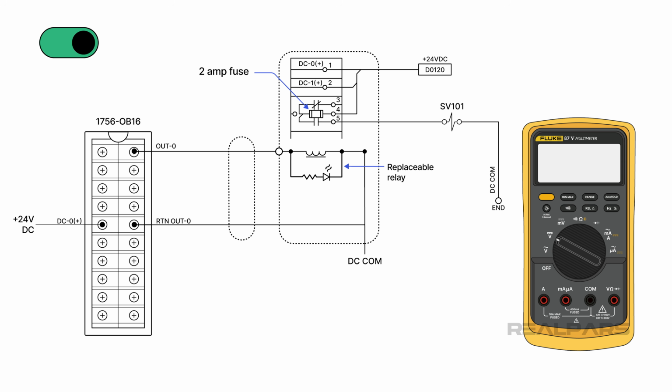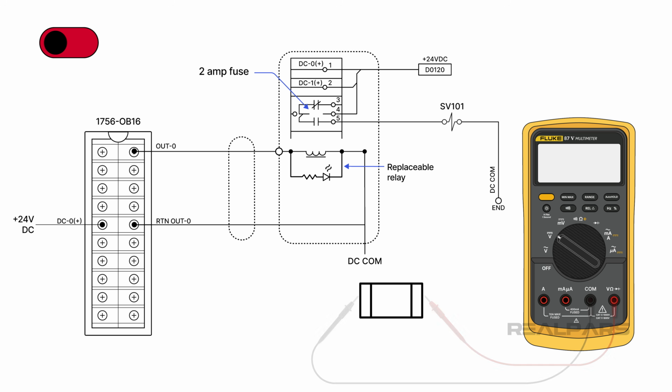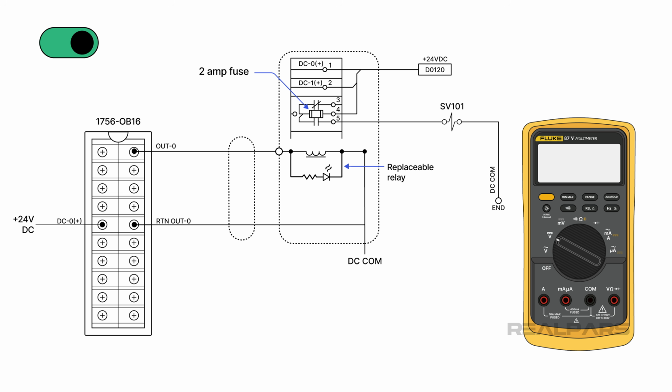Alright, if we don't see anything obvious, it's time to take some measurements with our digital multimeter. Many troubleshooters might start by testing the fuse for continuity, assuming it might be open. That requires interrupting the circuit and removing the fuse. There is a better and faster way to isolate a potential open circuit. We'll use the divide and conquer half-split method.